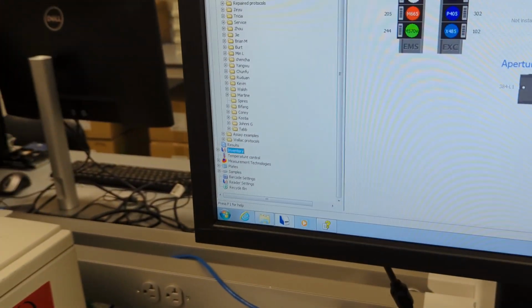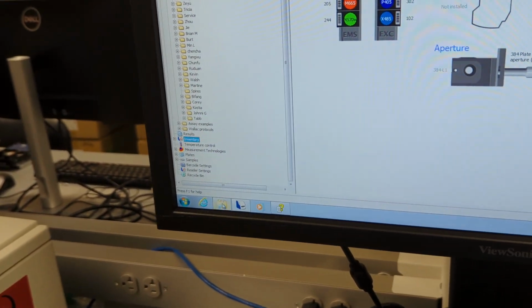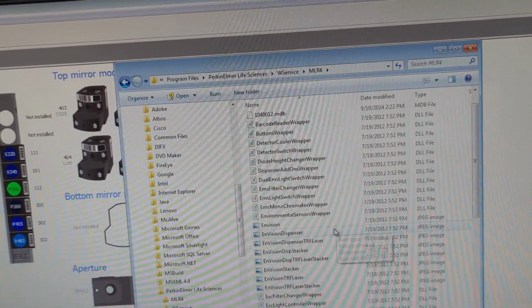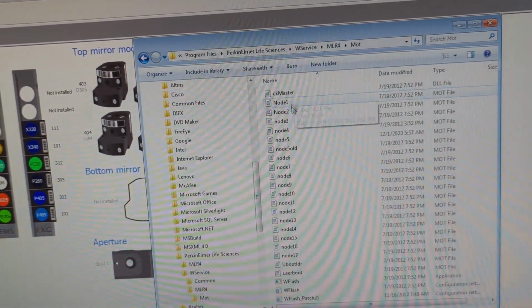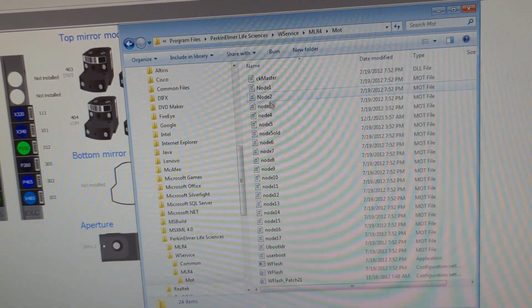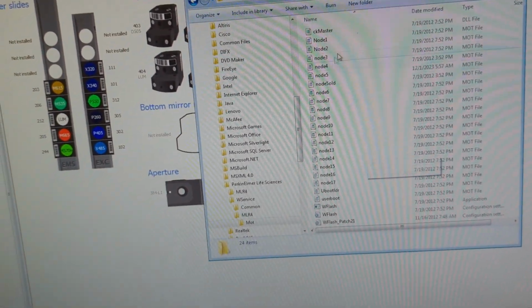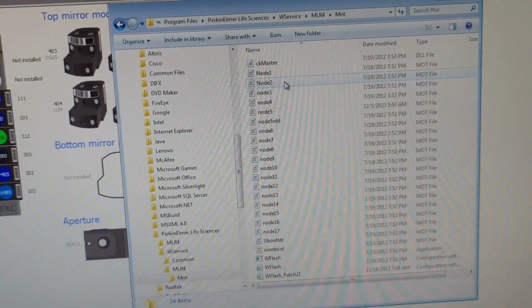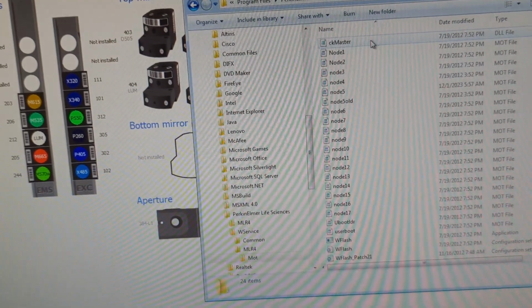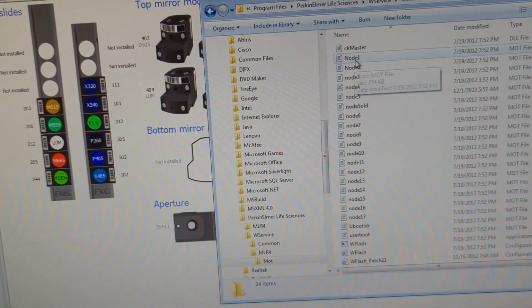They're not read protected, and the instrument actually stores the hex files for each of these, or MOT files, right on the instrument. So here's your MOT folder. This is for all of the node boards. You've got the programming code right here. And so if ever one of these fails, you can easily just pop it back on. Now, it can be a little bit difficult to do that because you really would have to use a Renesas development tool to do this.